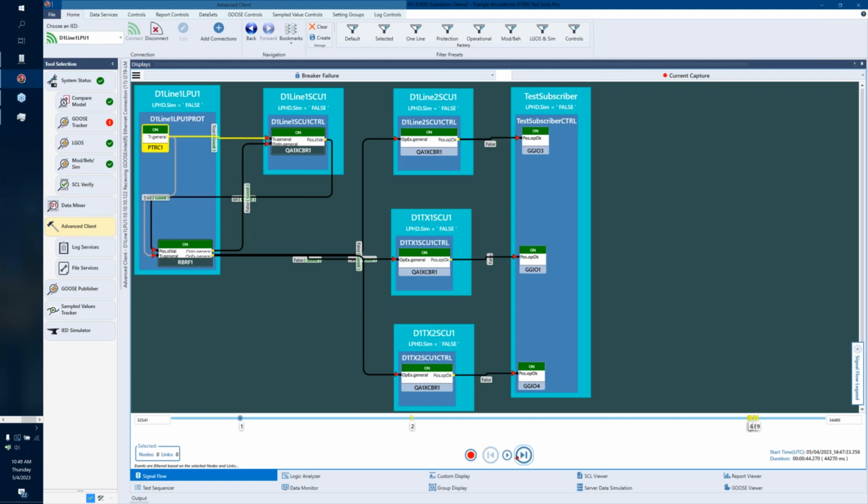Now, of course, because it doesn't, we can see that the RBRF sends an op in general, which in this case we're using as a secondary trip, which is being passed up to the XCBR. So just in case the first one didn't work, hopefully this one will. And he's going to go ahead and begin a second timer to wait and see if the position value updates.